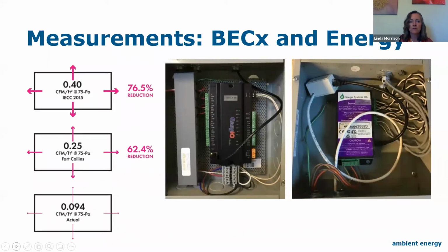After the building was built, some measurements were taken. So part of this shows the data loggers to assess the energy that's used in the building. And over on the left-hand side are some statistics about infiltration. So the IECC would allow 0.4 CFM per square foot at 75 pascals. The City of Fort Collins has a lower code than that at 0.25 CFM per square foot at 75 pascals. What they actually achieved was 0.094 CFM per square foot.